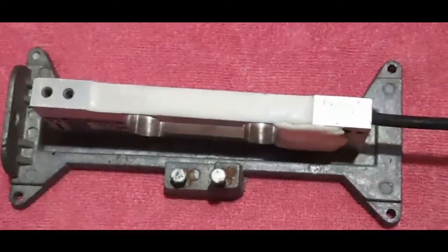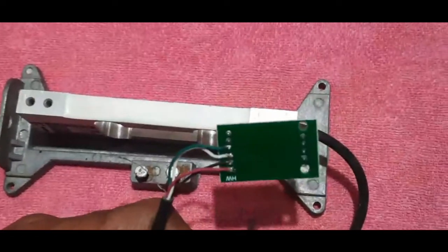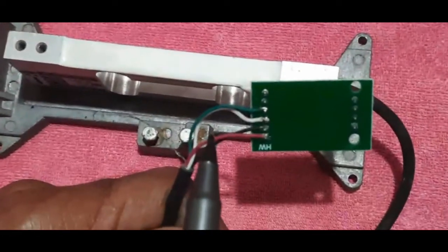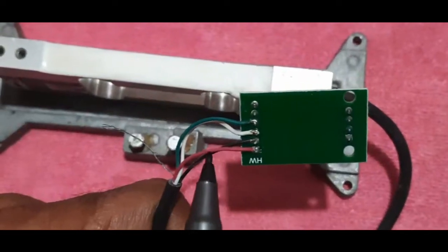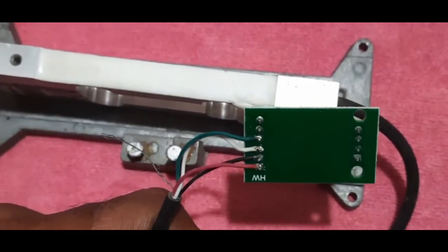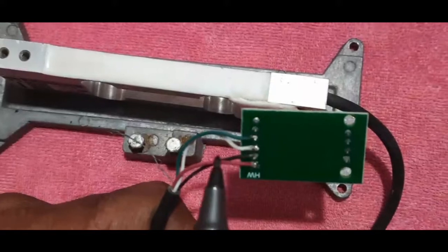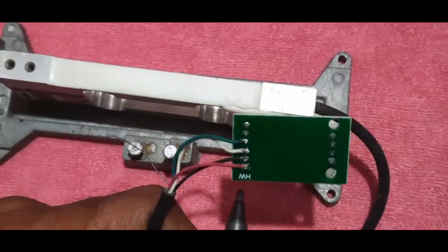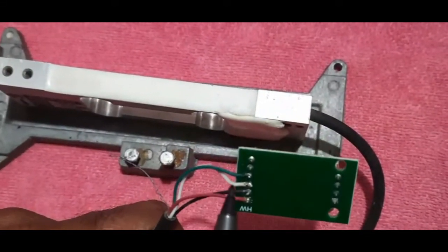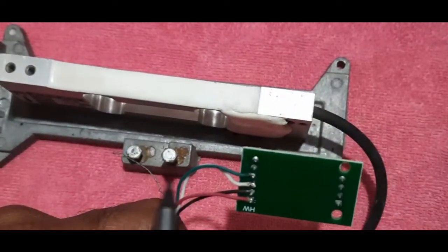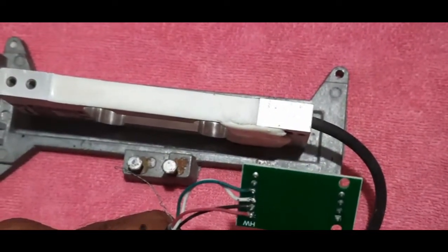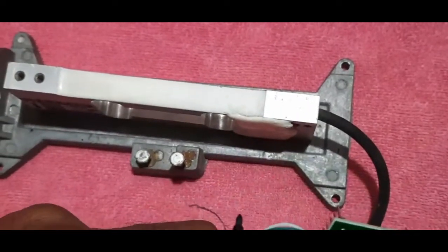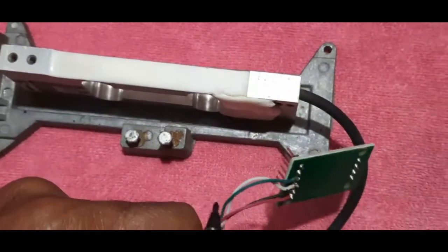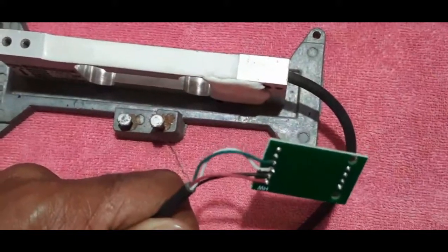This load cell has got 4 wires. Between the red and black wires, we give the excitation voltage, usually 5 volts, or we can use 10 volts, there is no issue. The output is the green and white wires: green is the plus output, white is the minus output. There is one more wire, which is the shield.